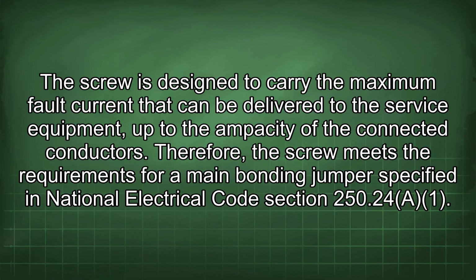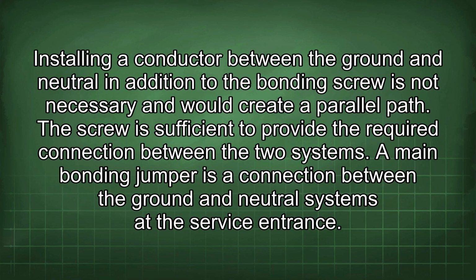Therefore, the screw meets the requirements for a main bonding jumper specified in National Electrical Code Section 250.24(A)(1). Installing a conductor between the ground and neutral in addition to the bonding screw is not necessary and would create a parallel path. The screw is sufficient to provide the required connection between the two systems.